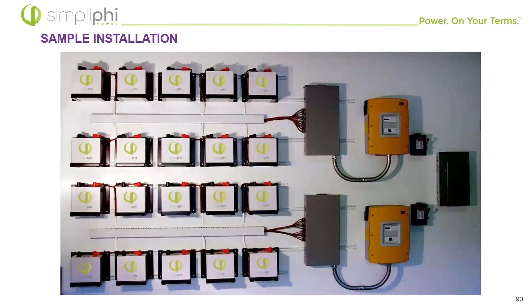One thing to keep in mind is that these cables are all supposed to be of identical length and gauge, as we mentioned. That means the batteries closest to the combiner box will have the most slack. So typically, whether or not you're using a cable tray, you can zip tie them. That's perfectly fine, as long as the idea is to keep all the conductors of equal length.